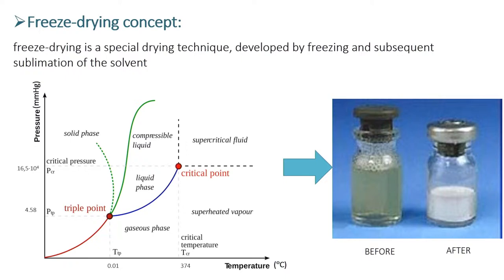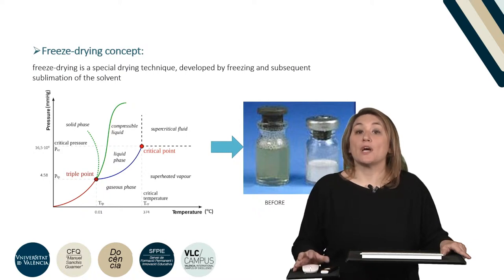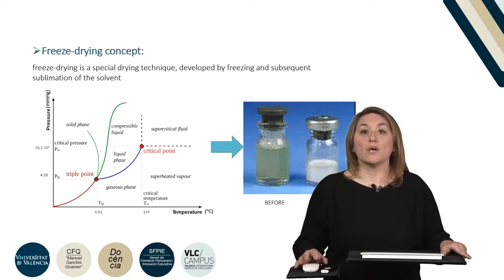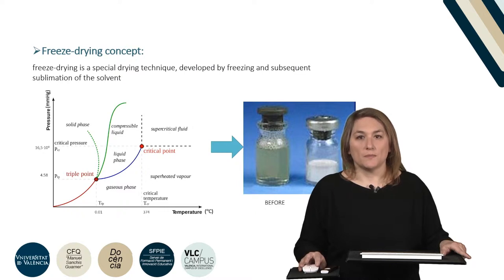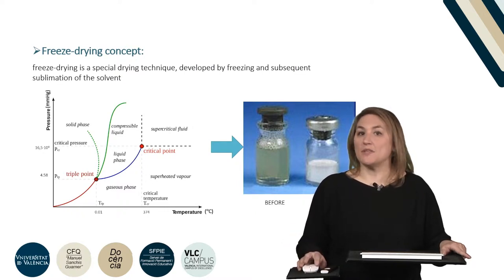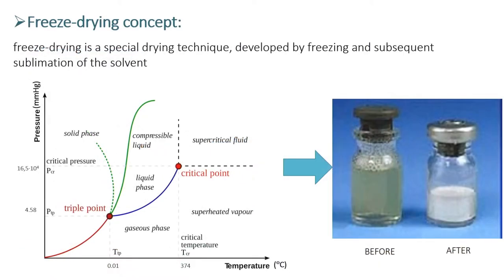If we look at the graph on the slide, we can see that the lower the pressure, the lower the temperature at which the ice begins to sublimate. In addition, if we work at pressures below the triple point, we can avoid the liquid state. Looking at the three-phase diagram, we can see that at pressures close to vacuum, the ice would begin to sublimate at a relatively low temperature. Therefore, working conditions at low pressures allow moderate temperatures, which make this drying optimal for thermolabile products.